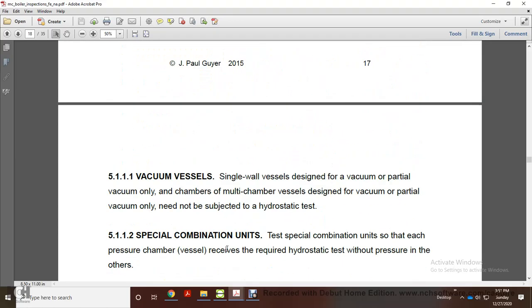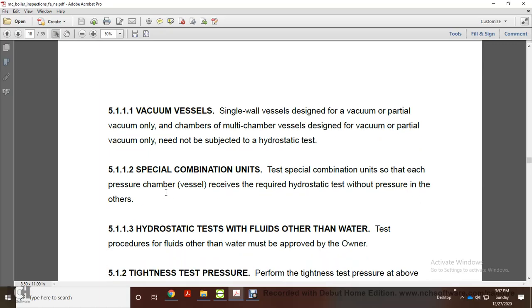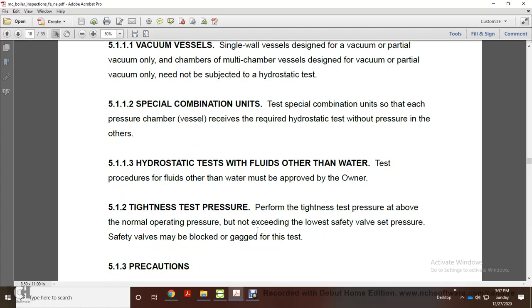Vacuum vessels: single wall vessels designed for vacuum or partial vacuum only. Multi-chamber vessels designed for vacuum or partial vacuum only need not be subject to a hydrostatic test. 5.11.2 Special combination units: in a typical special combination unit, each of the pressure vessels is required to be hydrostatically tested without pressure in the others. 5.11.3 Hydrostatic test with fluids other than water. Test procedure fluids other than water must be approved by the owner.